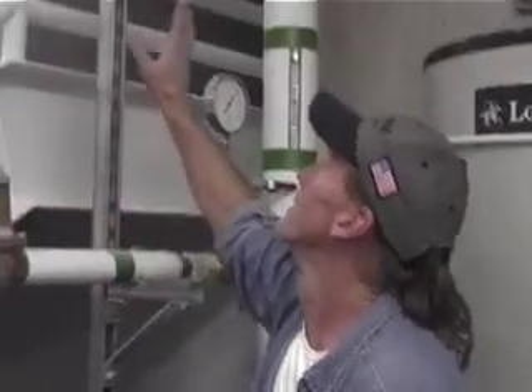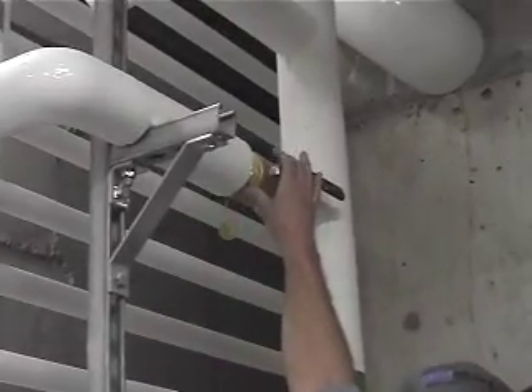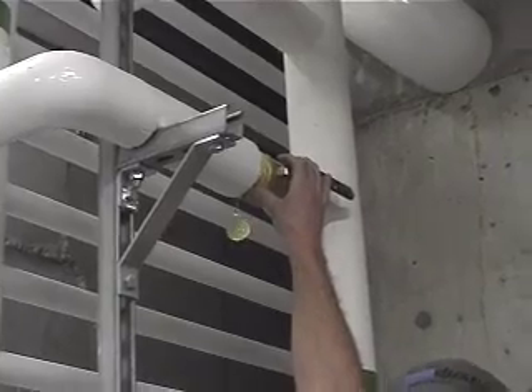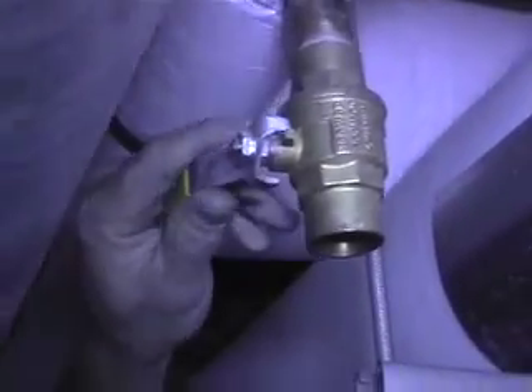This is Kevin with PAT Mechanical. We're going to be talking about the shut-off valve for the makeup water to the cooling tower that's outside. There is a 2-inch valve right here. This is the valve that you want to shut off in the wintertime when you do your draining. And then up here in the tunnel, up the stairs, you'll shut that valve off out there. Come in here and you can open up this ball valve right here and it'll drain down into the sump, and that will drain all the makeup water that goes from the cooling tower back to here, so we don't have any freezing under the ground during the wintertime.